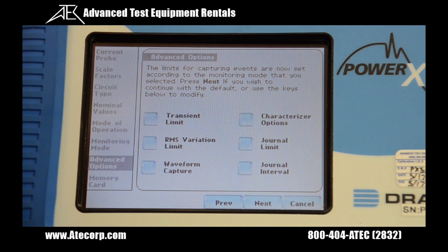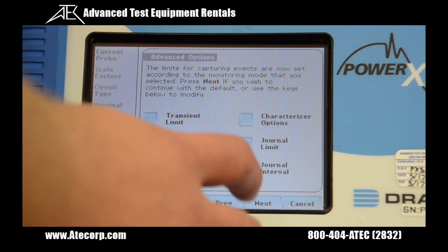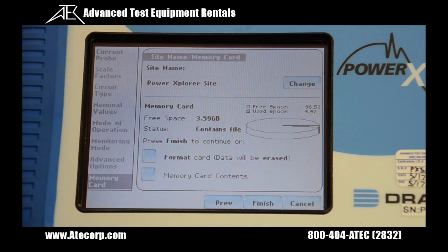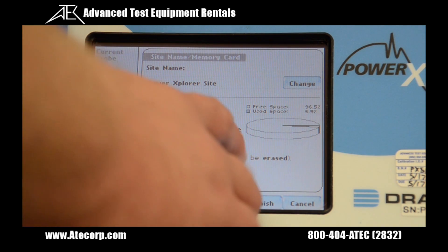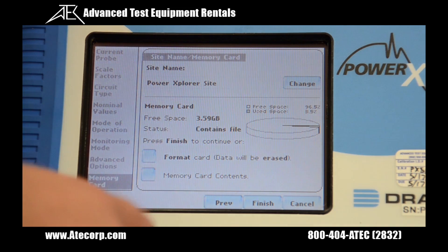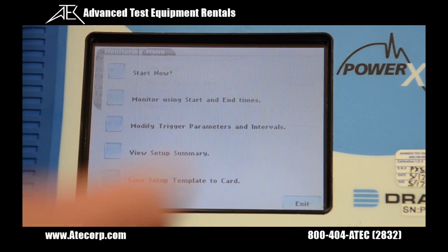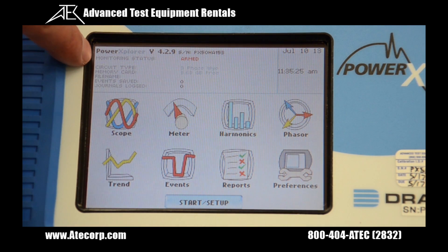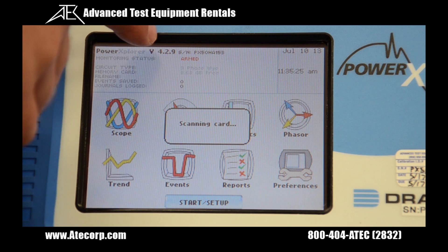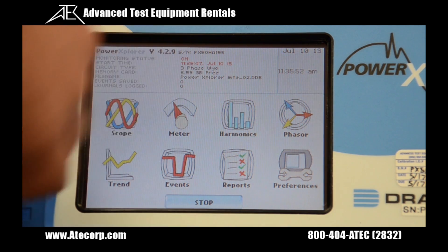We get advanced options. From here we can modify our various limits. Hit next again. From the memory card screen it shows our memory card and allows us to format the SD card — if you do this the memory will be erased. We can look at our memory card contents, and once everything is set we hit finish to start recording. Hit start now. Now you can see our monitoring status on the top is red as it says armed, and it is now recording as monitoring status says on.